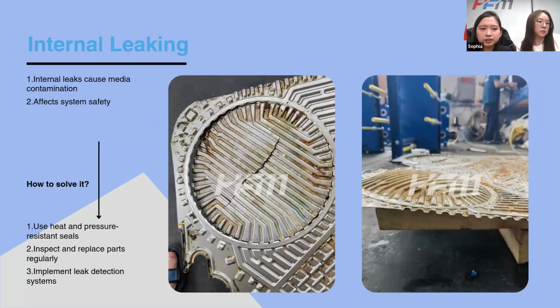And as you can see in the picture, here is internal leaking. Internal leaking refers to poor sealing between the channels inside the heat exchanger, which leads to leakage of the heat medium and affects the heat exchange effect and system safety. We can solve it by using heat and pressure resistant seals, regularly inspecting and replacing deteriorated parts, and designing a leak detection system to repair problems in a timely manner.